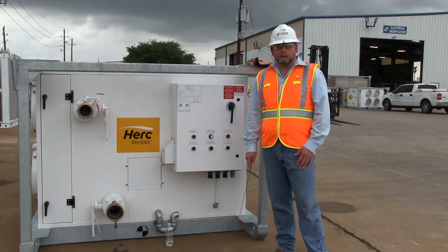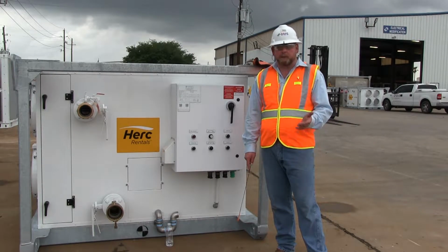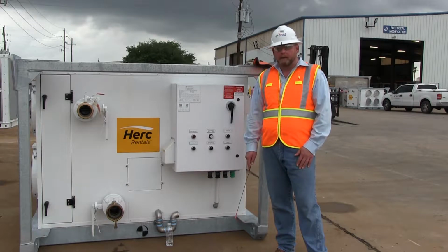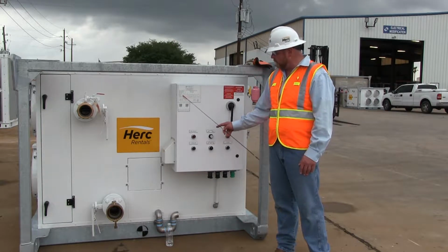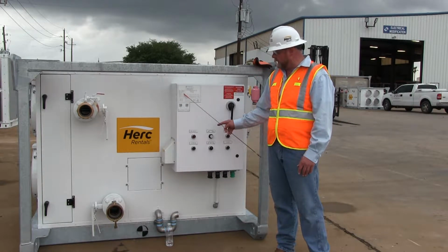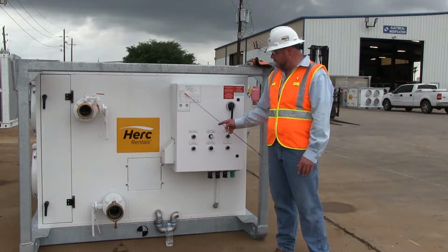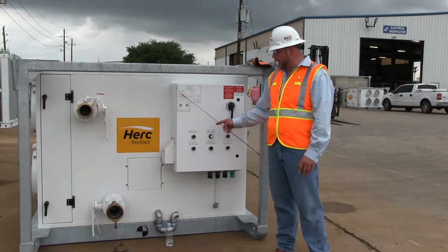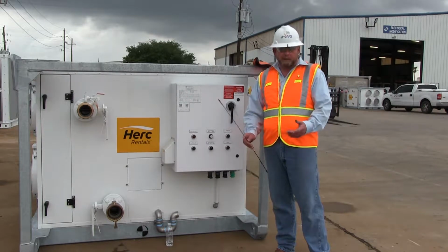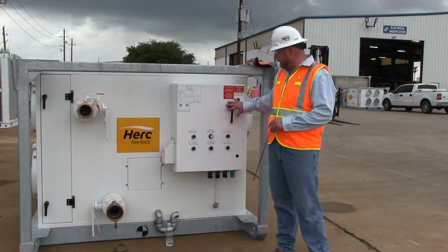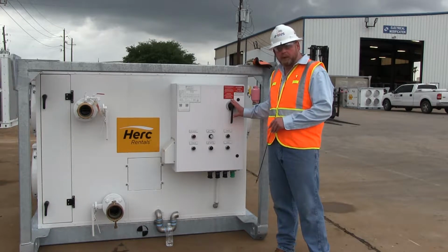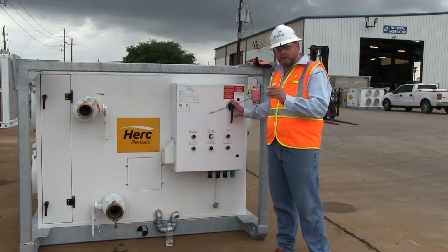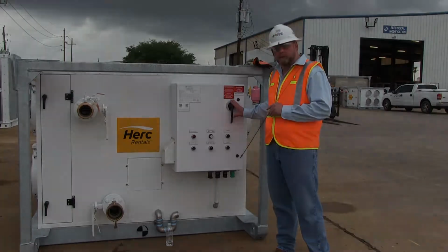The 50-ton chilled water air handler requires 460 volt 3-phase 60 hertz power. In order to identify what you need here for power requirements, you simply look at the tag. You'll notice that this unit needs a minimum circuit ampacity of 19 amps and the maximum overcurrent protection is 25 amps. All the CAPS manufactured equipment has an integrated built-in circuit breaker, so you're only going to need to protect the circuitry of the power and the cabling coming to it.